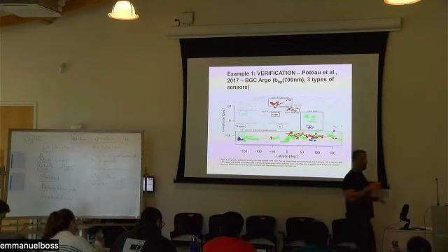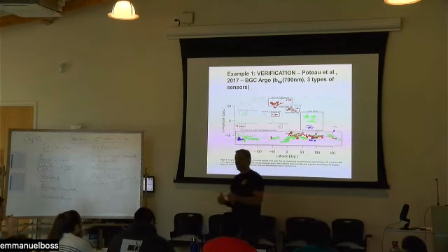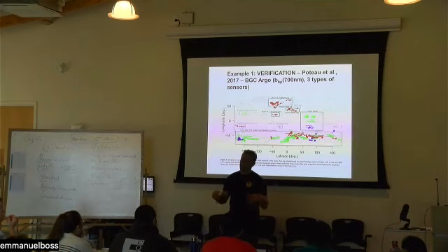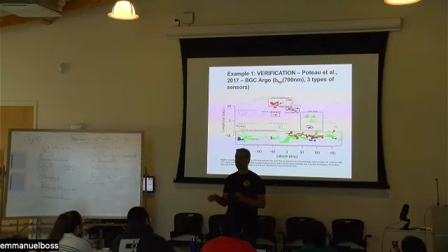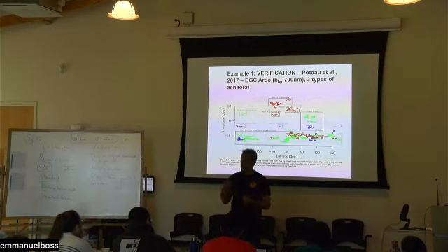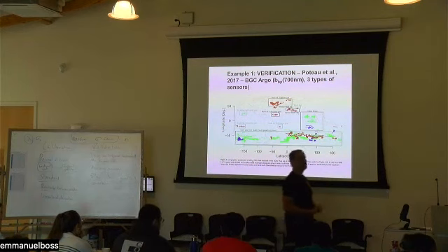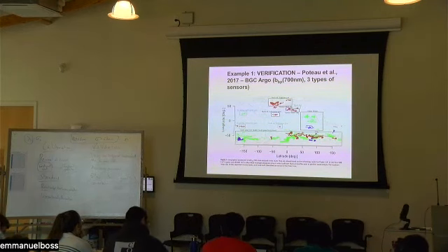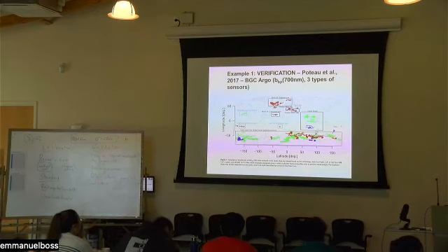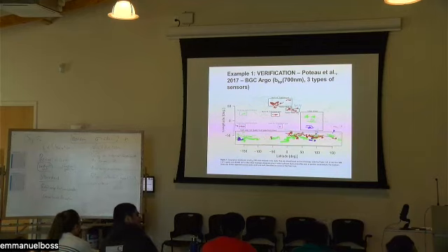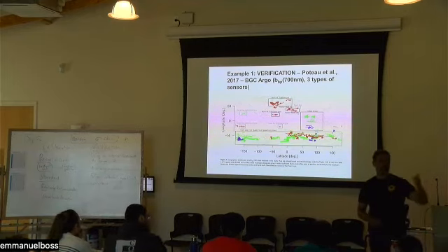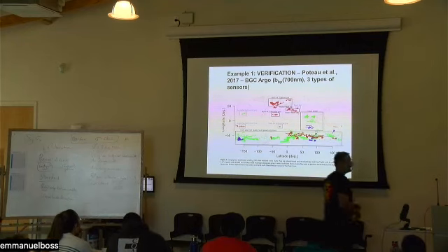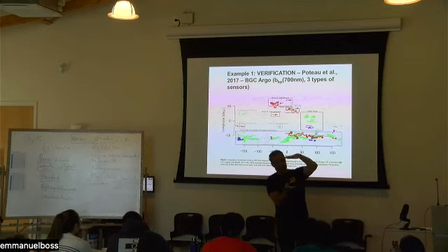They have different angles, and all of those are calibrated with beads. Well, that's not quite correct. The way they should be calibrated is with beads, but the way WET Labs did it is they would have what they call a golden sensor, on which they spend the $300 to calibrate with the beads, and then every other sensor was cross-calibrated to that sensor. Periodically they check the beads again on that sensor. I think they cross-calibrate with a formazin dilution series or something like this, something stable that they can buy commercially. But you're right, there might be an issue with that. But that's much cheaper. For $50, you get a thing like this as opposed to that.